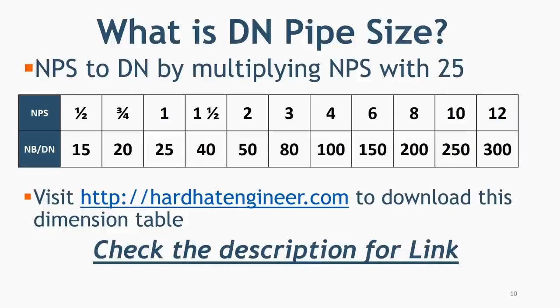What is pipe schedule? Pipe schedule is the way pipe wall thickness is mentioned. To simplify the ordering of the pipe, ASME committee has developed schedule number which is based on modified Barlow's wall thickness formula. The schedule number indicates approximate value of expression 1000 times P by S, where P is the service pressure and S is allowable stress, both expressed in pound per square inch.